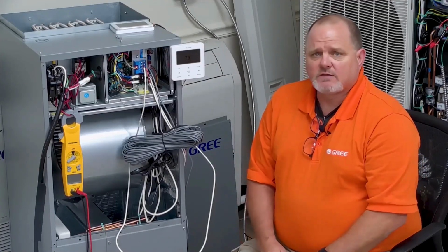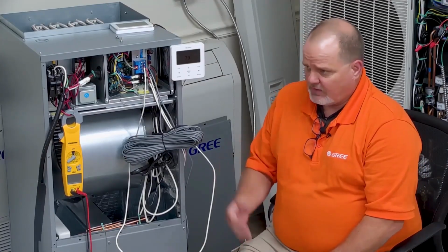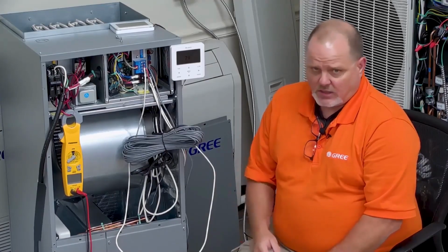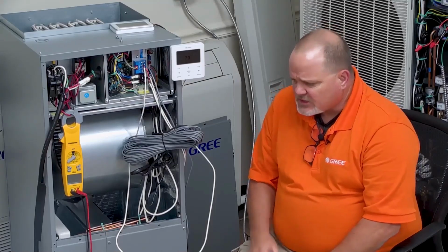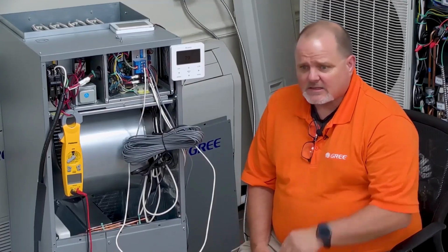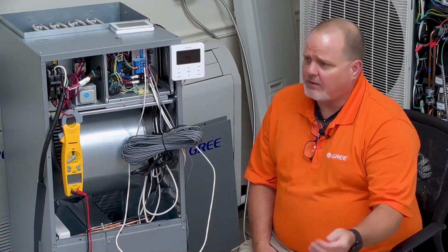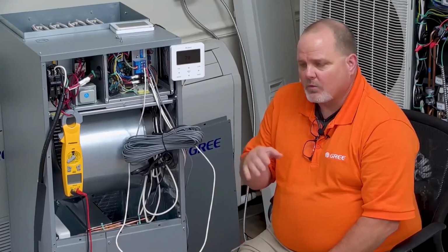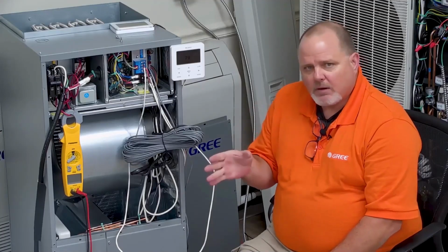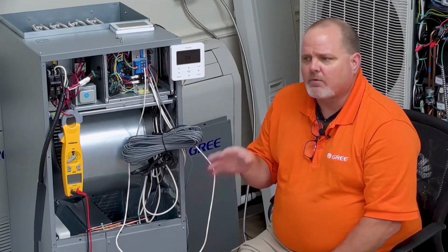The E-heat function gives them the ability to still have heat in the house, running just the electric heat until the serviceman gets there to fix it. Auxiliary heat is exactly that. It's auxiliary to the heat pump. So for auxiliary heat to work properly, the way that works is the heat pump is heating. That's your first stage of operation.